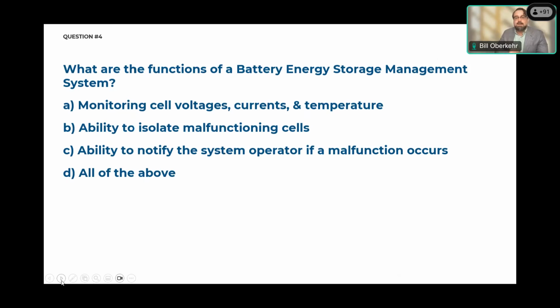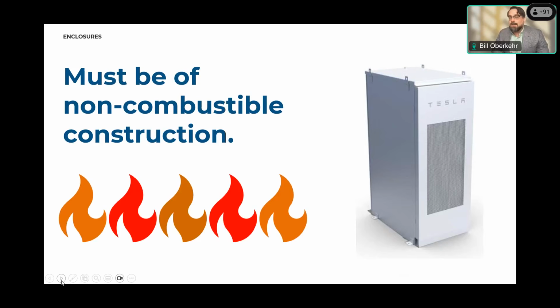This one might feel like a no-brainer, but it is required by code nonetheless. In 1207.3.5, all ESS should be made of non-combustible material. This is to contain a fire if it should happen within the enclosure, so the heat does not transfer to other enclosures. That will, as Paul said, be validated by data from the UL 9540A large-scale fire test report.